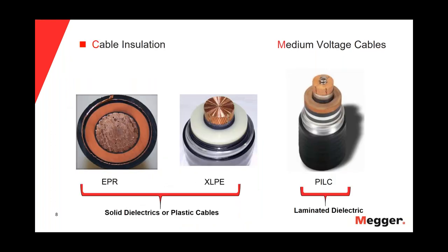Regarding the insulation for medium voltage cables, we have the solid, dielectric, or polymeric insulation. You can see on the left of the slide the EPR and the XLPE insulation — these are maybe the most common insulations found nowadays in medium voltage cables. And on the right, you will see the paper-insulated cable, which can also be found very often in medium voltage installations.